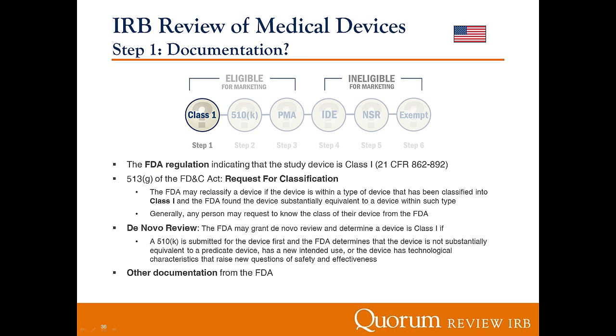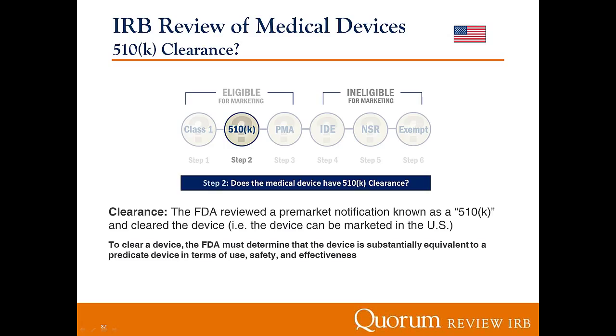Now moving on to step two. If the device is not Class 1, then does the medical device have 510K clearance? What a 510K means is the FDA has reviewed an application for a device and has determined that the device is substantially equivalent to a device that's already being marketed, what's known as a predicate device. Most people with device trials try to get that clearance from the FDA, a 510K, because a 510K is typically much simpler than going to the next step and having to do pre-market approval, because you don't have all those different efficacy requirements. You just have to show with a 510K that you have a device that's substantially equivalent to a device that is already on the market. So if the FDA says, yes, we agree with you, it is substantially equivalent to a device already on the market, then the device is considered cleared. Not approved, but cleared. That's a very important distinction. The FDA doesn't want to say it approved it, it said it cleared it.